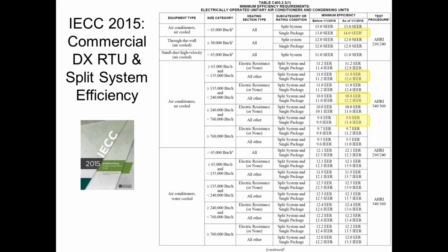And then as the units go up, as you can see I have highlighted in yellow there, as the sizes go up, I will become more and more lenient on what the requirements are because the manufacturing volume is not as high. But I'll still have to do both. I'll have to have the full load and the part load efficiency. And generally the smaller units need to be more efficient than the bigger units.